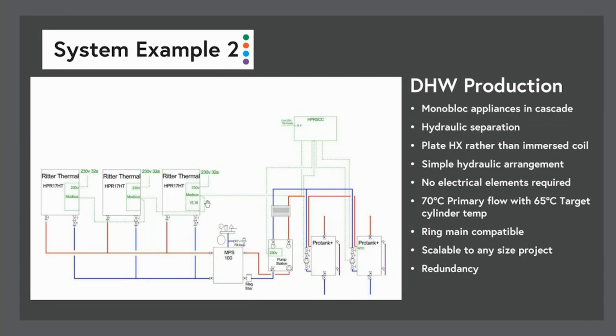And as I said, if this was a domestic system, you maybe only have one heat pump on the side and maybe one cylinder on this side, but the actual setup of the configuration of this would be very, very similar, if not identical. The nice thing about having multiple heat pumps in a bigger job would be the scalability of it. So you can just increase the number of heat pumps required to meet the load. You've also got redundancy. So if this was a very, I guess, high risk environment, so you're producing hot water for industrial application or for sanitary use in, say, a hospital or aged care facility, then you can generate redundancy in the system by having multiple units. And if one unit goes down, then the other units can take over while the unit that's had a problem is repaired.